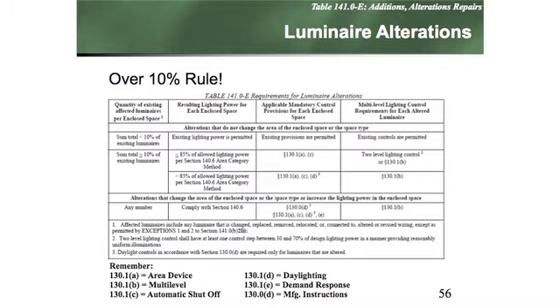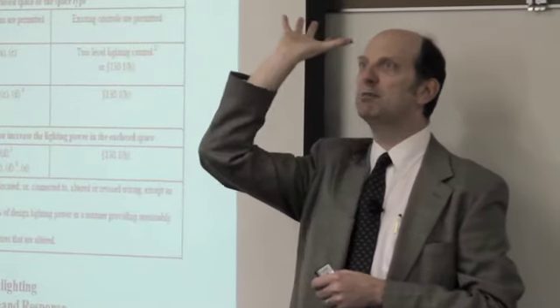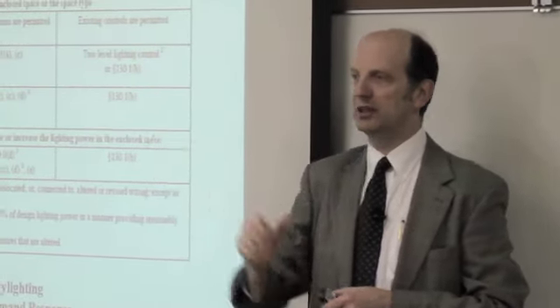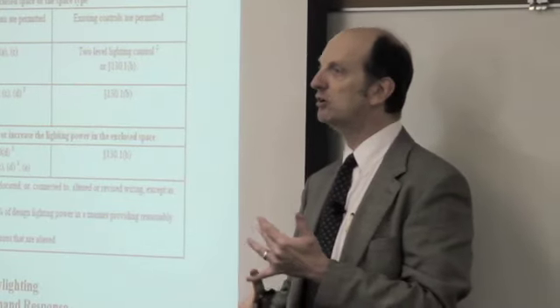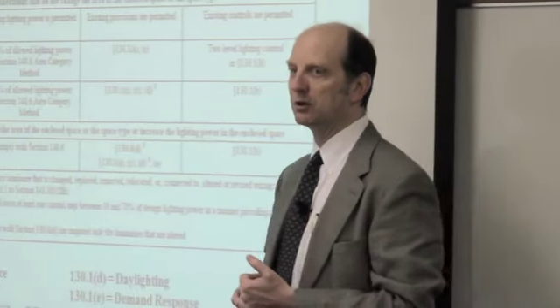And here I have to do the multi-level requirement, which means I might, if I don't make it super efficient, have to put dimming in now. So I touch 2 fixtures and I have to put controls in, including dimming controls, for this whole space, if for a school I'm above 0.7 watts per square foot.